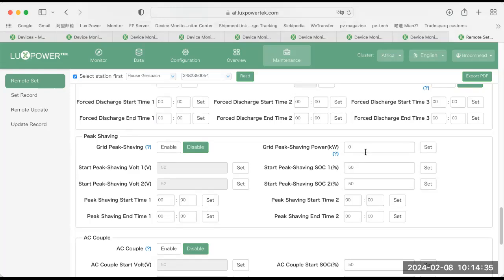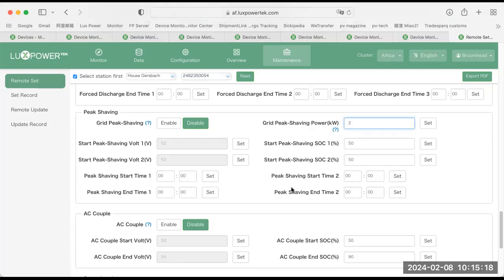So basically what you can say is here, if we hover over there, it tells you that you can set the maximum power that the inverter will draw from the grid. So in other words, if I set this, remember that this is in kilowatts, right? If I set this to 2 kilowatts, it simply means that when PV is on, or is it PV and battery, but at any given time, the maximum power it will bring from the grid is 2. The rest of the power it will draw from battery and PV, right? And then you can obviously set your battery limitations here, and you can set the times during which you want your peak shaving to start. And the reason we put this function in here is, especially in Europe, they have different tariff times, so the customers can set their machines according to the different tariffs that are set by the utility.